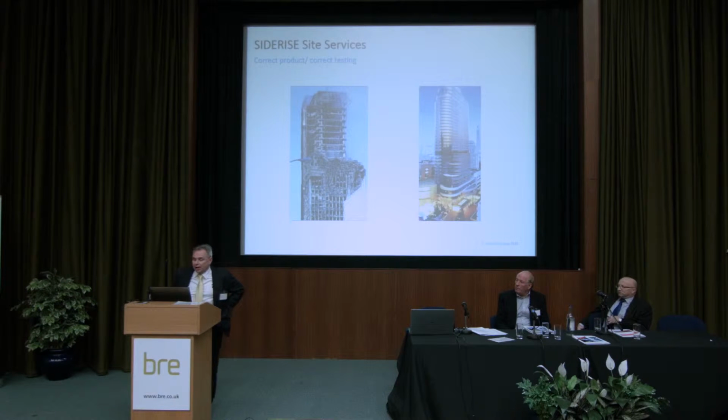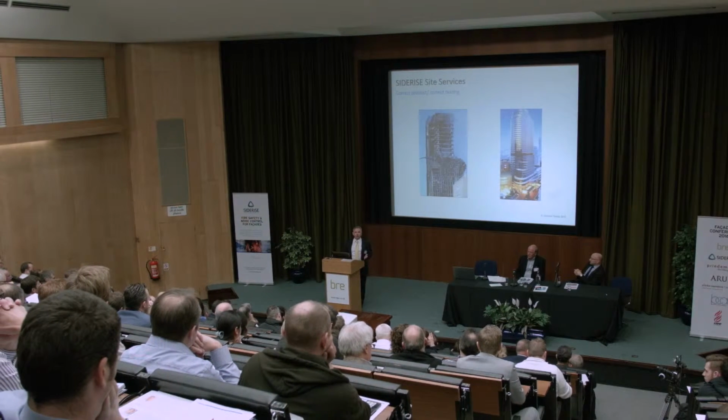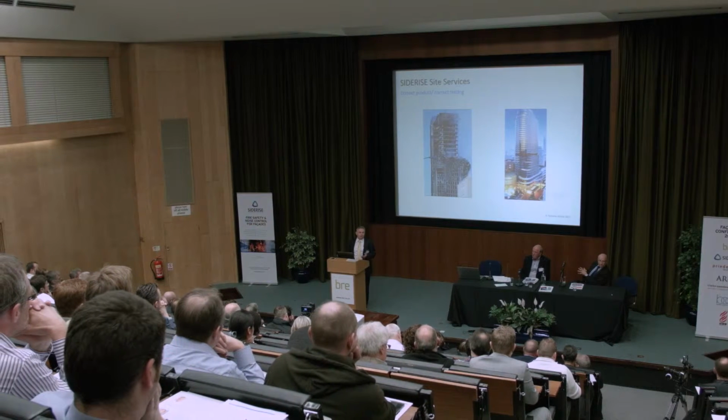There's a number of reasons why the fire spread through there, and I don't want to get into any particular discussion now about what test methods you should be testing fire barriers to. What I would say, though, is that curtain wall facades move. If you look at one of the main documents that any facade contractor gets, it will talk about the specification, and movement through drying, shrinkage, creep, thermal movement, all of those sorts of things that play on the facade. If that facade is moving, then any fire stop that sits between the facade and the slab edge is going to have an imposed load acting on it. If it can't accommodate that load over a long period of time and it breaks down and fails, then when a fire occurs, the chances are that it's not going to stop the fire spreading between the slab edge and the facade. So it's very important for you to consider with the products that you're installing, will they accommodate the movement over the long term of the building?